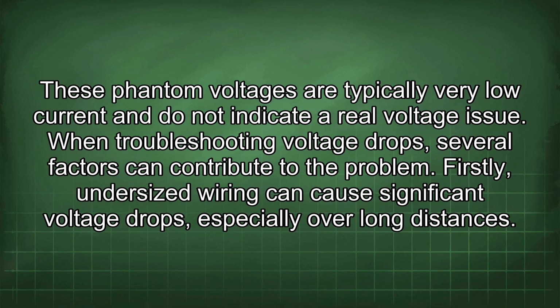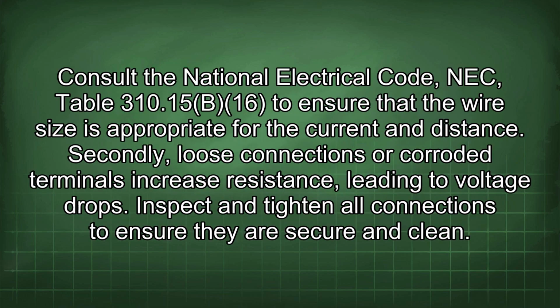When troubleshooting voltage drops, several factors can contribute to the problem. Firstly, undersized wiring can cause significant voltage drops, especially over long distances. Consult the National Electrical Code, NEC, Table 310.15(B)(16) to ensure that the wire size is appropriate for the current and distance. Secondly, loose connections or corroded terminals increase resistance, leading to voltage drops. Inspect and tighten all connections to ensure they are secure and clean.